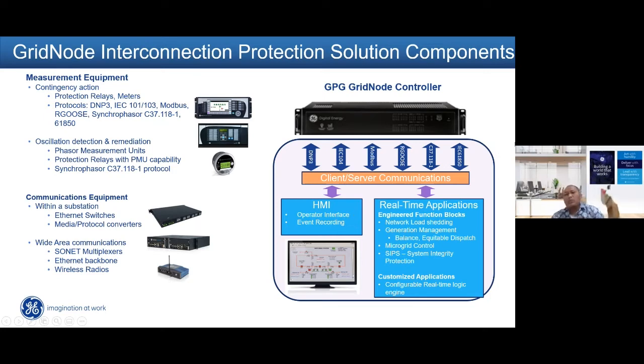And also inside this GPG controller, it has real-time application engineered function blocks such as network load shedding, generation management, microgrid control, SIPS, and also a customized application such as a configurable real-time logic engine. And then related to the measurement equipment, for example, for the contingency action solution, we have our products such as a protection relay and meter, which also comply with the protocols of DNP3, IEC 101, 103, Modbus, R-GOOSE, Synchrophasor C37, and also protocol 61850.